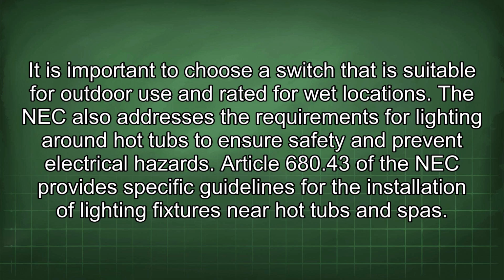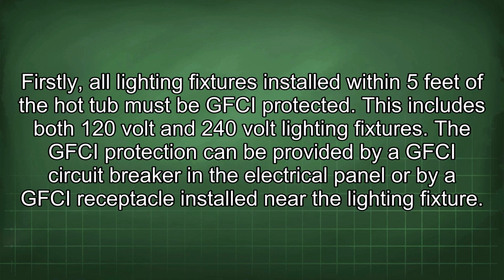The NEC also addresses the requirements for lighting around hot tubs to ensure safety and prevent electrical hazards. Article 680.43 of the NEC provides specific guidelines for the installation of lighting fixtures near hot tubs and spas. Firstly, all lighting fixtures installed within 5 feet of the hot tub must be GFCI protected. This includes both 120-volt and 240-volt lighting fixtures. The GFCI protection can be provided by a GFCI circuit breaker in the electrical panel or by a GFCI receptacle installed near the lighting fixture.